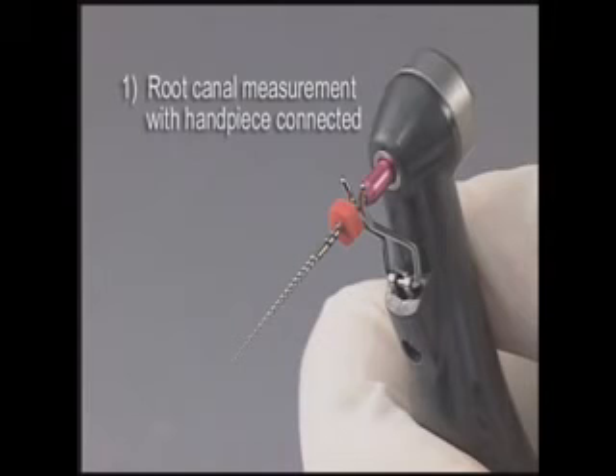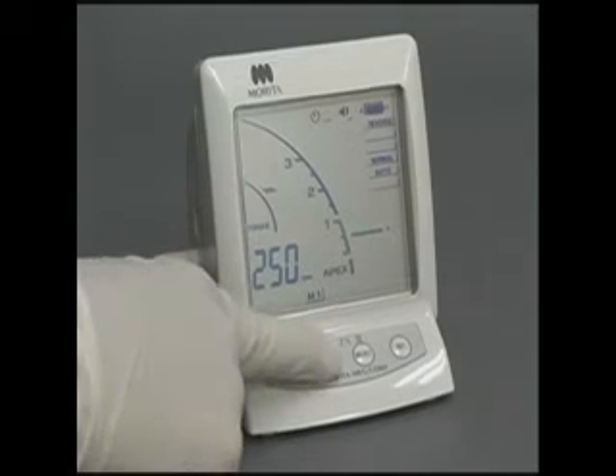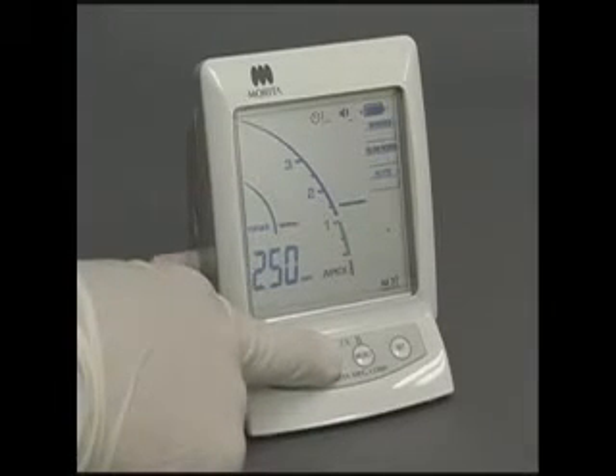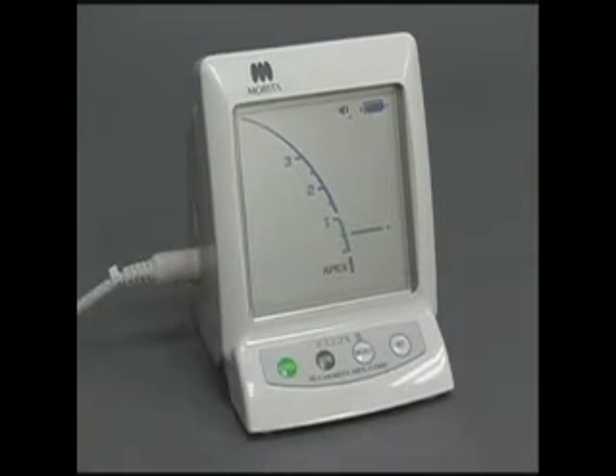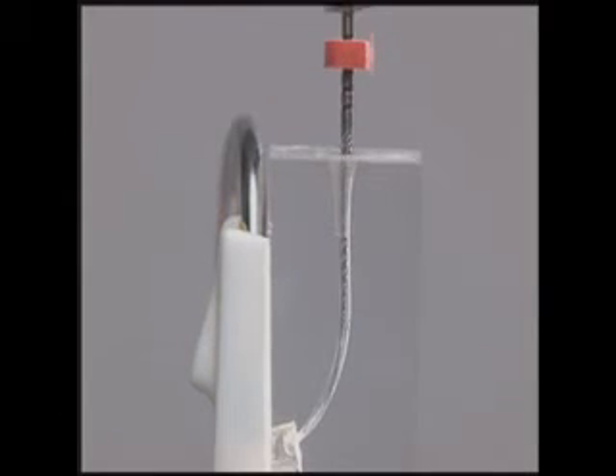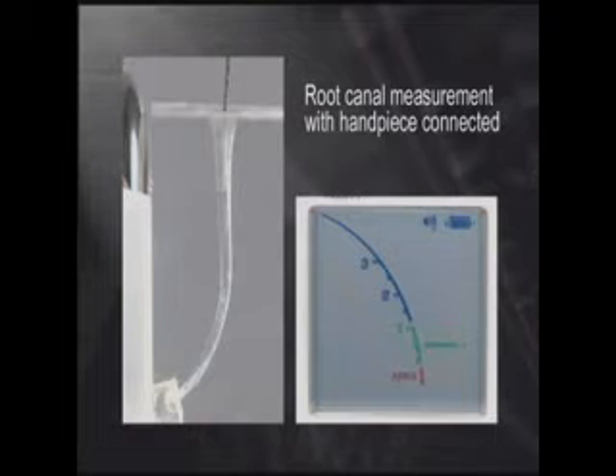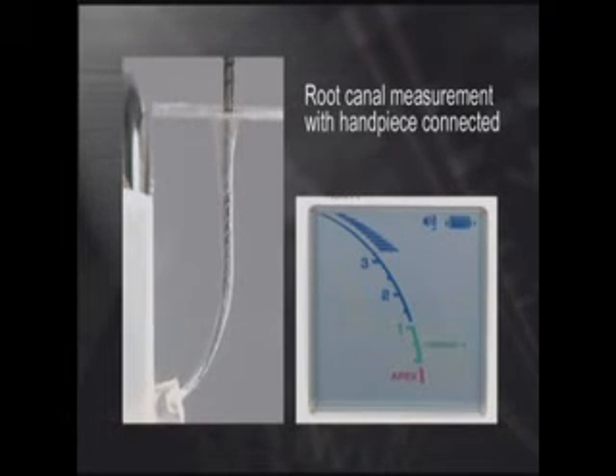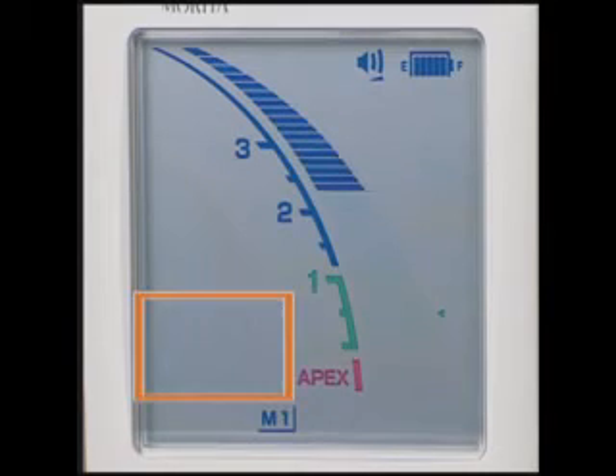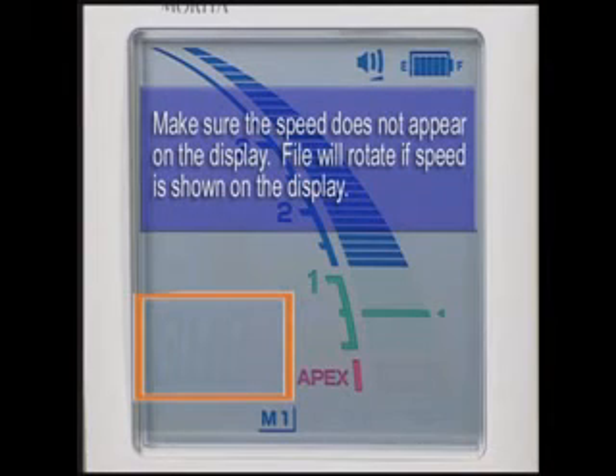There are two methods available for the canal measurement using the low-speed handpiece module connected to the canal measurement module. First, leave the micromotor connected to the unit and press the mode switch until speed and memory displays disappear. Under this condition, the file will not rotate when it is inserted into the root canal, and only canal measurement will be performed. Make sure the speed does not appear on the display. The file will rotate if speed is shown on the display.